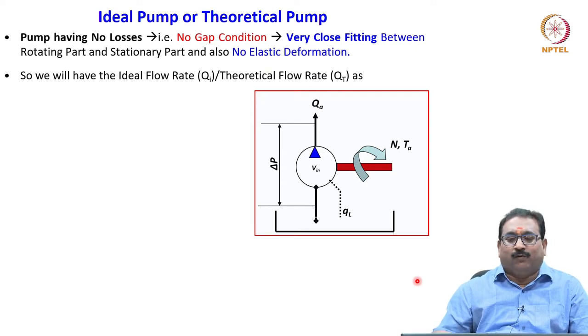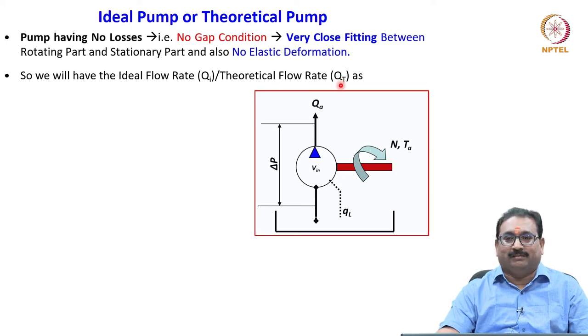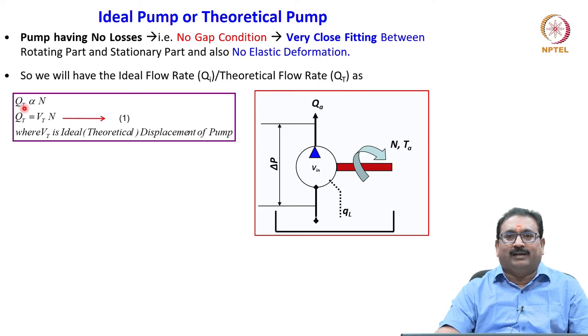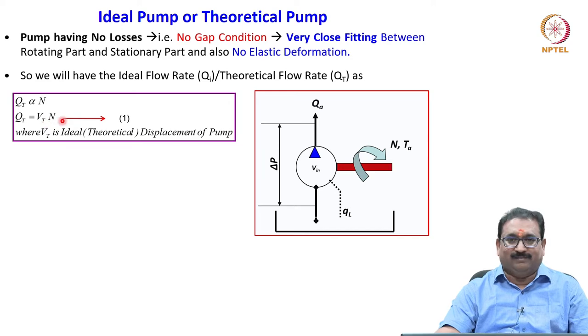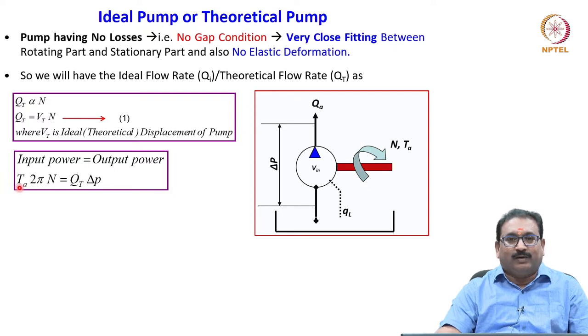We will have an ideal flow rate QI, also known as theoretical flow rate QT. The theoretical flow rate is directly proportional to speed N, or QT equal to VT into N. The input power given is equal to TA into 2π N, which equals QT — the theoretical flow rate — multiplied by delta P.